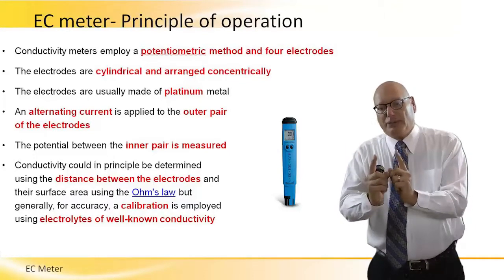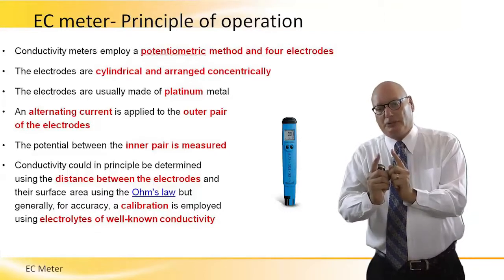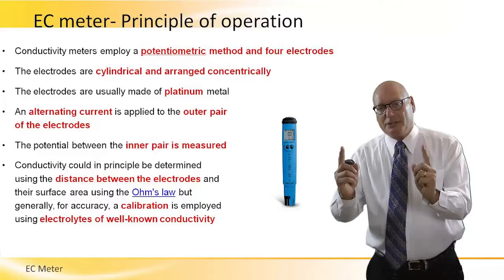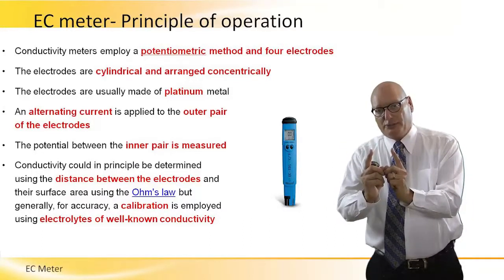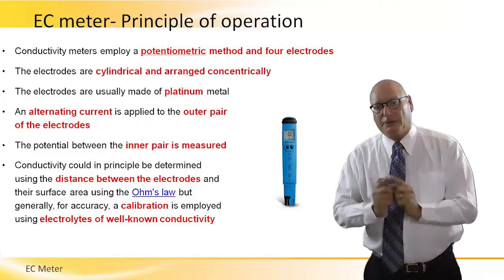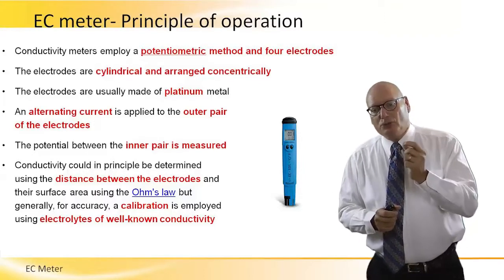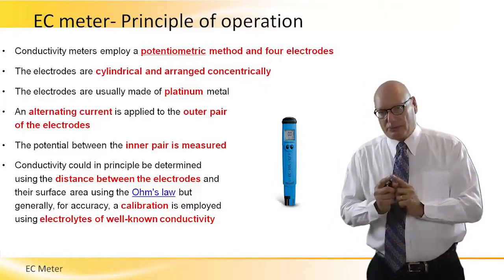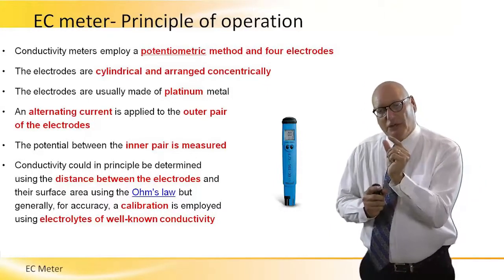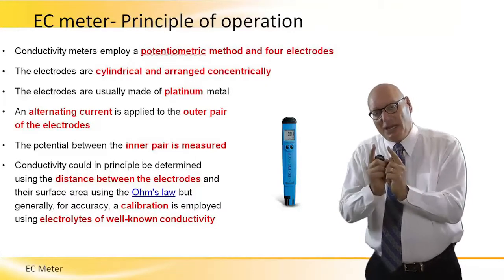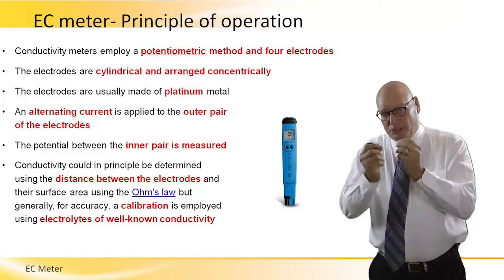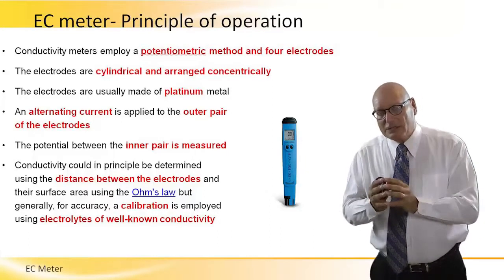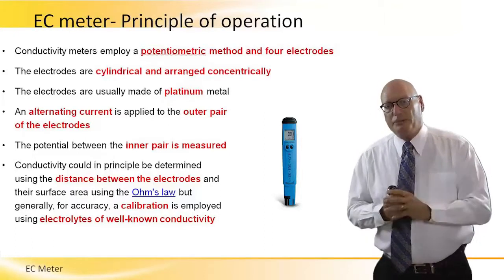The potential between the inner pair is measured. So we conduct AC power to the external pair, and we measure the potential difference in the inner pair. The conductivity should, in principle, be determined using the distance between the electrodes. There is a certain reference distance between the inner electrodes, which is actually used when we calibrate the device to measure the conductivity of the solution.